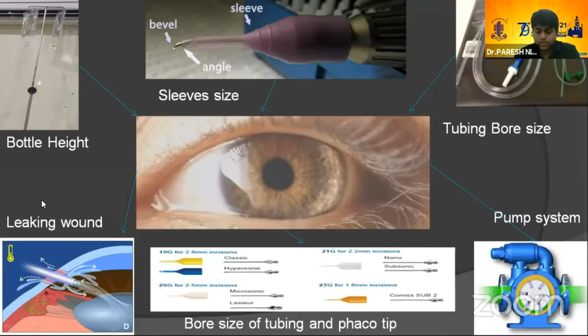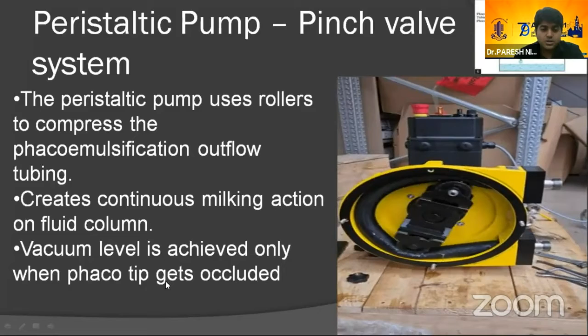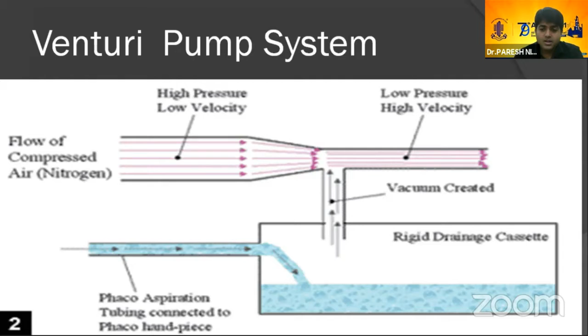If we talk about the different pumps, there are majorly two pumps. The first is the peristaltic, which is the most commonly used. The peristaltic pump basically uses a roller which compresses the phaco tubing, creating a continuous milking action, which is responsible for the aspiration of the fluid from the eye and generation of the vacuum once the tip is occluded. Whereas in the Venturi pump system, high pressure, low flow air is transmitted to make low pressure, high velocity, creating a vacuum which is transmitted to the eye via a rigid drainage cassette.